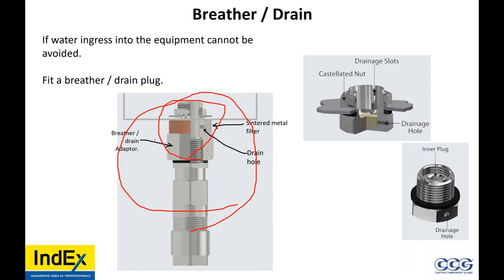Breathing is not allowed at the bottom, right? No. If you have one breather drain installed at the bottom of the equipment, it breathes, but not as efficiently as it could. So if you have a spare entry with a plug in there, I would install a breather drain. It's not going to be at the bottom, it's not going to be at the top, it's going to be halfway in between, depending on the mounting of the device.